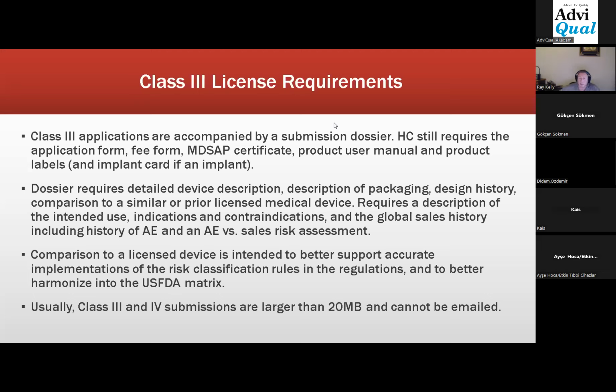This is one place where Health Canada does leverage a little bit a safe sales history, a performance history of the device outside of Canada, as one of the things they consider. With Canada, it's interesting because not every single test report and document, like with FDA, is required. They're going to make a decision based on all of the documents provided. So, if you didn't do this test or you didn't do that test or you don't have a clinical study, it doesn't mean that the device won't be approved. It just means that your argument or justification for the device to be approved is a little weaker.